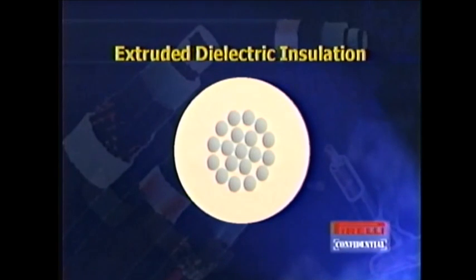Now in a medium voltage cable, if you put a dielectric material directly over the conductor, you have some problems. The reason you have problems is because you have a fairly high voltage stress. On low voltage cables where the stresses are not that high, you can extrude a dielectric material directly over the conductor and pretty much have no problem. You've achieved the purpose of keeping the voltage from shorting to ground, and that's the end of it. You increase the insulation thickness on low voltage cables mainly for mechanical purposes, but it takes very little insulation and is very low stress.